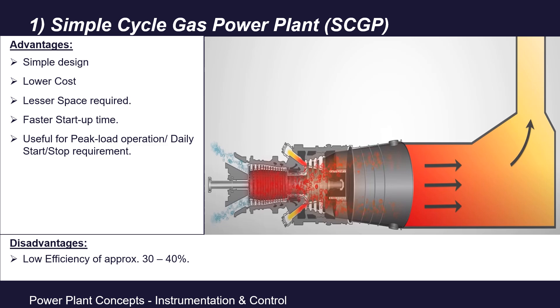Regarding the disadvantage: the fuel gas chemical energy is converted into heat energy in the combustion chamber, then into mechanical energy to rotate the blades, which then generates electricity. But the exhaust gases are vented to the atmosphere and are still at a very high temperature and pressure. So only approximately 30 to 40 percent of the chemical energy of the fuel is converted into electricity — the rest is wasted. A simple cycle gas power plant has a very poor efficiency of only 30 to 40 percent.